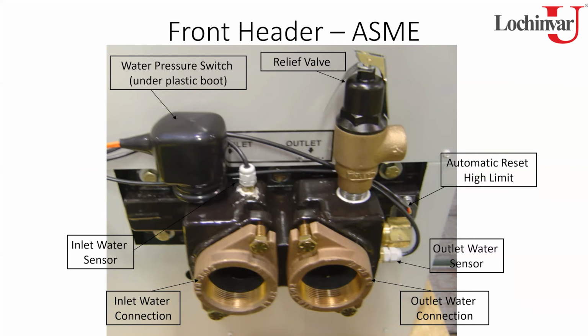And also on the ASME header, I forget if you pointed this out or not, kind of follow along with me. You can see this bronze plug that's screwed into the right side of the header where the outlet is. That plug turns into a stem, and that stem goes through a spring and attaches, and it puts pressure onto the bypass that allows water to flow from the inlet to the outlet when flow rates are starting to increase. Right. So that actually has to do with your bypass inside of that header.